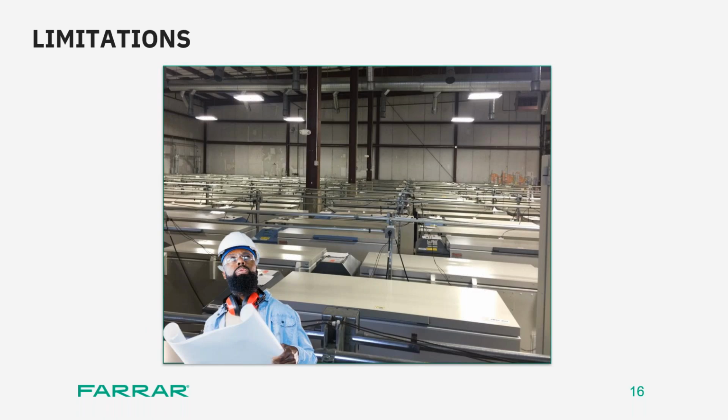Now, although the surrounding space to this freezer farm shown here is air conditioned, typical air conditioning is around 20 degrees Celsius. So every time you open a reach-in, maybe if it's at minus 70 or minus 80, that temperature delta can exceed 100 degrees. That's a huge heat load every time the door is opened, and it's only exacerbated more every single second that door is opened.